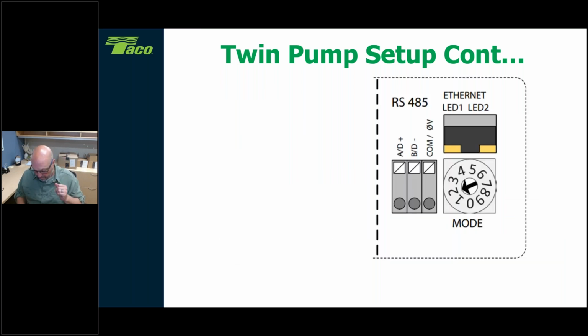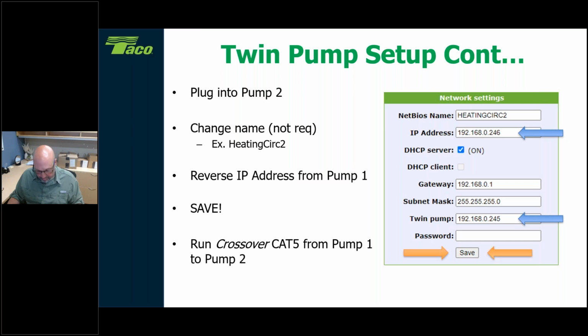These are little things you never really think of when you're going into this, that it's a different kind of Cat 5 cable. So it's an important point to remember. And even if you were using standard Cat 5 cables, you're still going to have to make them on site, because as you put the wires through the terminals, they're not going to have the ends on them. So you've got to push the wire through. The ends are still going to be made on site. Just remember, they're going to be crossovers there, and you can't do a standard Cat 5.